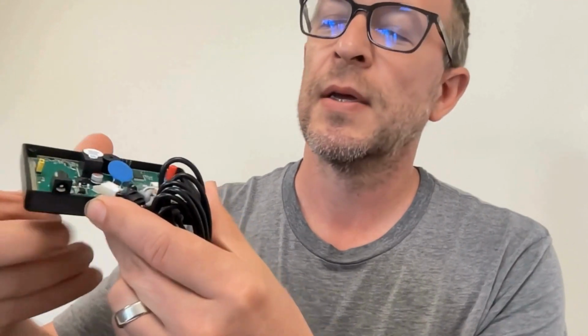So getting into some other common errors that come up. One of the most unfortunate ones that I really hate dealing with is water damage. Water damage indicator is going to be the too high and the too low red lights flashing with a constant beep, beep, beep, beep, beep. Usually what has happened, the reason I hate this one is because I always get a lot of pushback. Oh, I didn't get it wet. Oh, there's no way. It's mounted on the wall. 95+% of the time, what has happened is this power supply tip that plugs in here has landed in water. It was unplugged from the unit for some maintenance. It lands in a puddle or in the sump, and it gets plugged in wet.